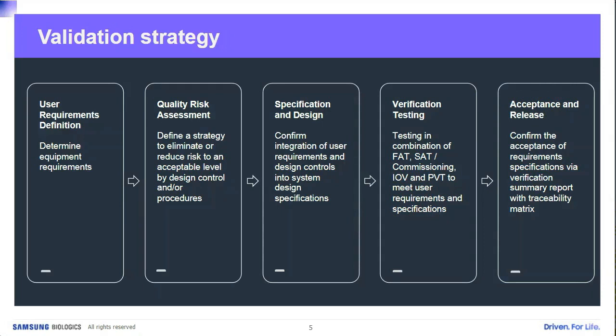In the past, we would do each one of these individually. So for a lyophilizer or freeze dryer, we would do a full factory acceptance test, then bring it on site, install it, do a full site acceptance test, and then repeat all those same tests again as part of the installation operational qualification.